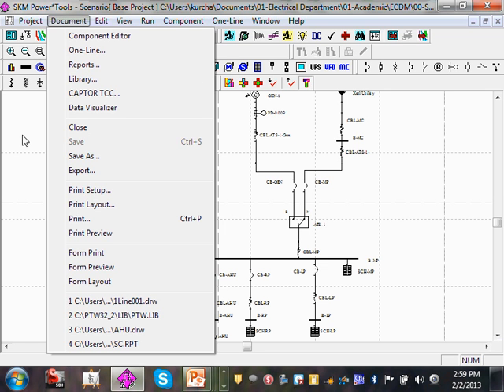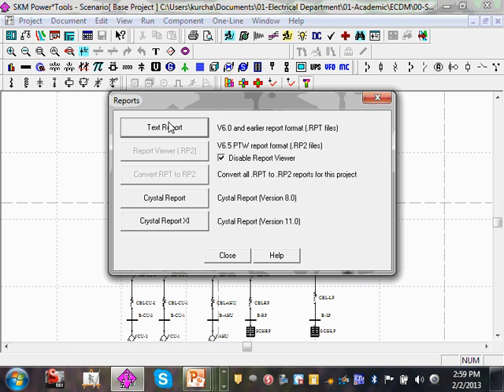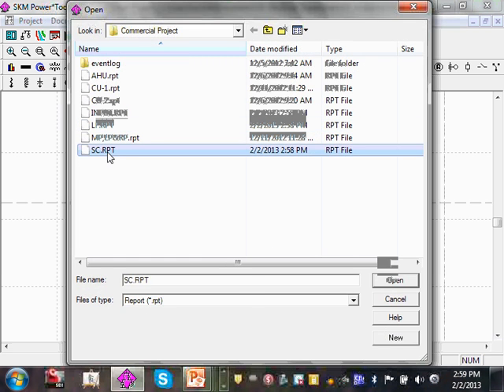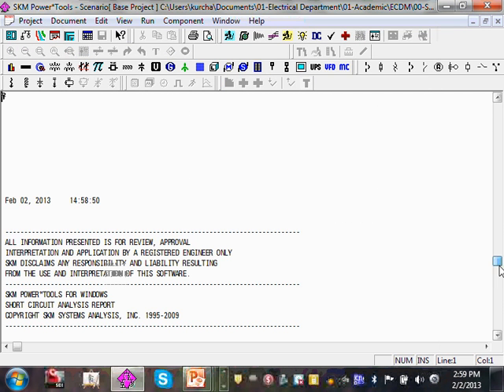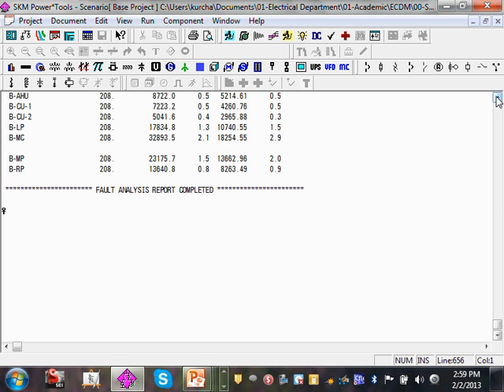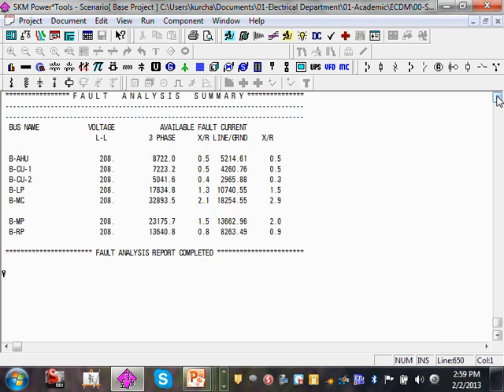Okay, so I'm going to go to the document. Here's my document and text. And here's the short circuit report that you get. Now after you did all this, I'm going to go all the way down to the bottom. Here's the single most important part. When it calculates based on impedance, you're getting the available short circuit. See, guys, available fault current, line to line voltage, 3-phase, line to ground. So let's go to bus main panel. MP is main panel. It's a 208 system. Here's how much current is available, 3-phase. Here's my ground fault, 13.6.